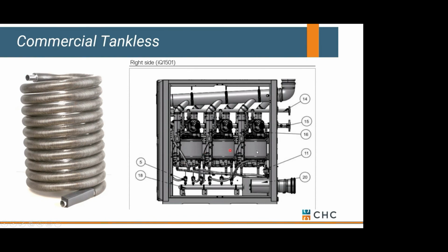In this case, they're going to take multiple engines that are usually 200 to 250,000 BTUs, and they're going to manifold them together. In this case, we've actually got 6 engines that are manifolded together. You can see 3 in the front and another 3 in the back. They make up about 1.5 million BTUs worth of water heating capacity. Pretty slick. It's a single point of connection for the system. It's a single vent run, single makeup air, single gas connection. Okay, and all that happens within this packaged unit, if you will.